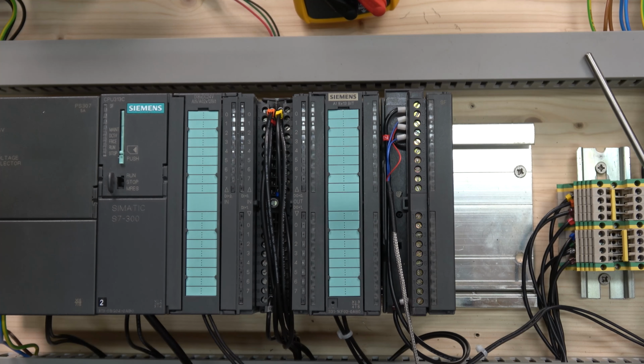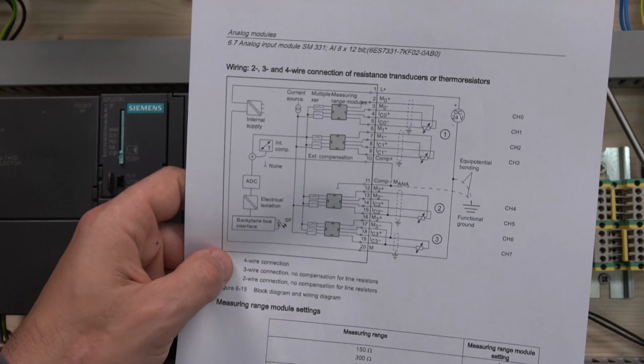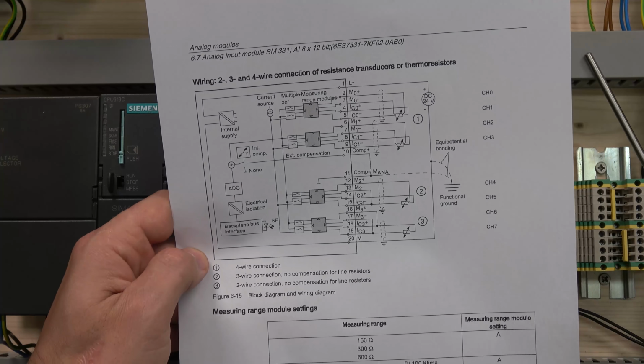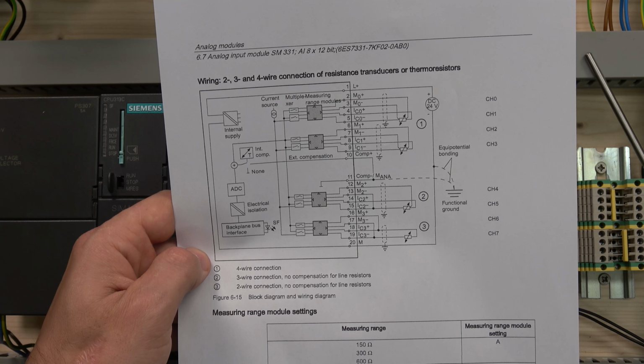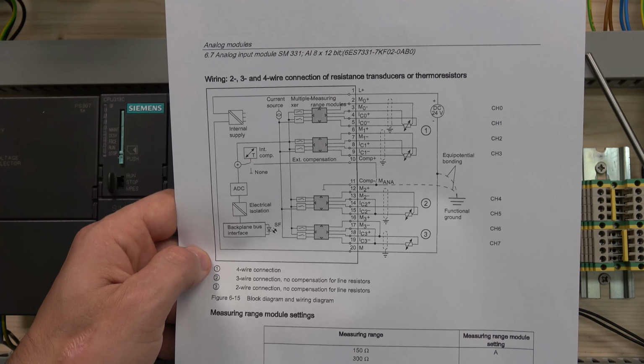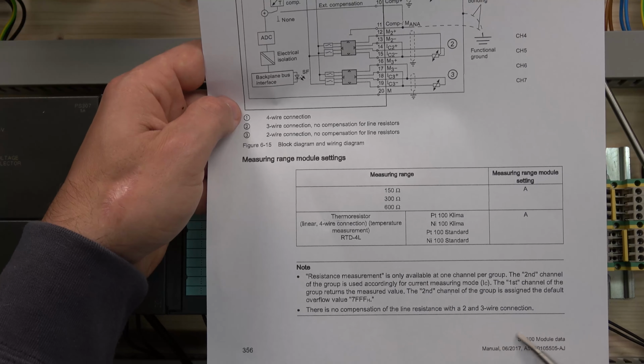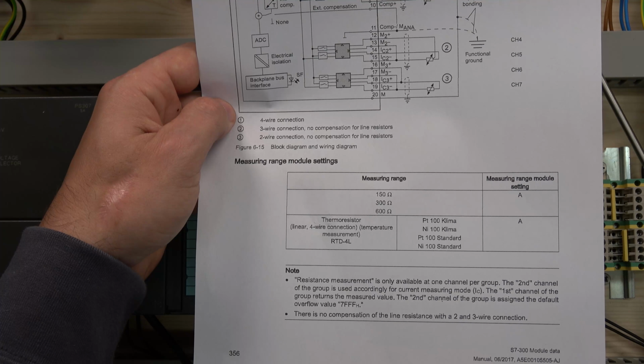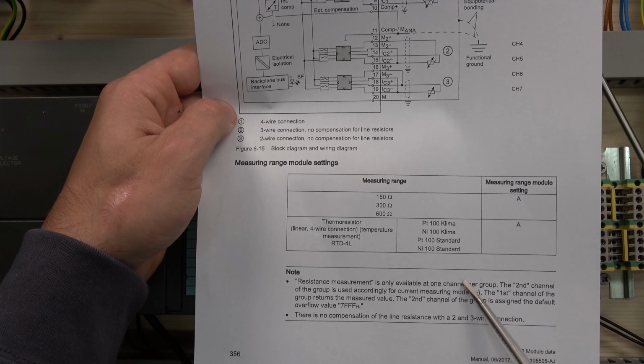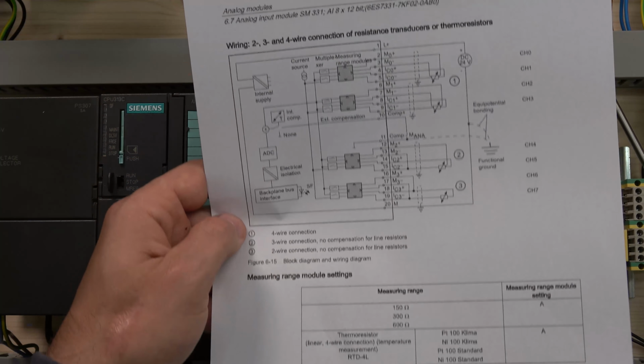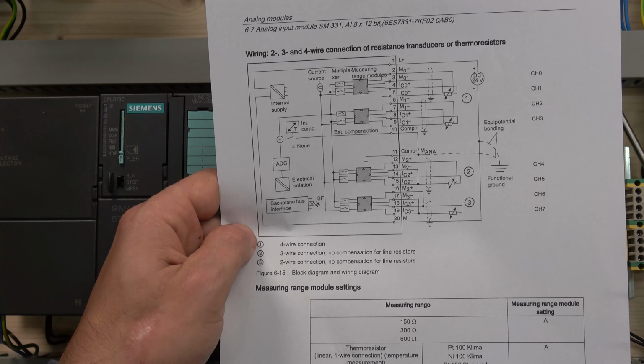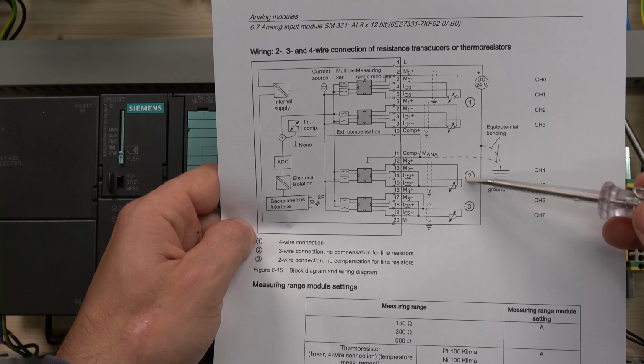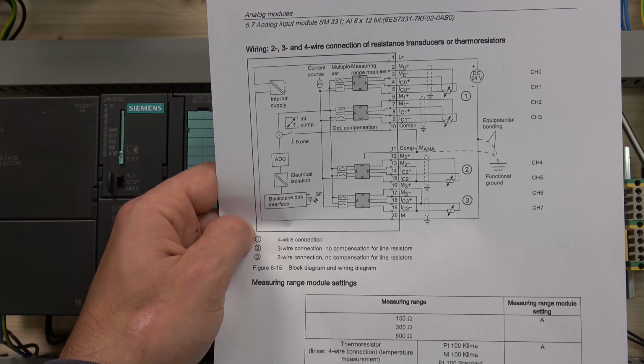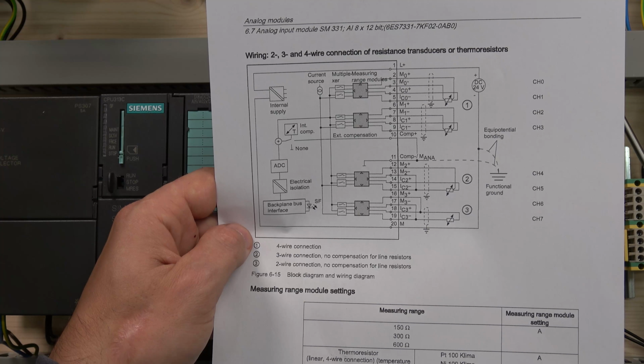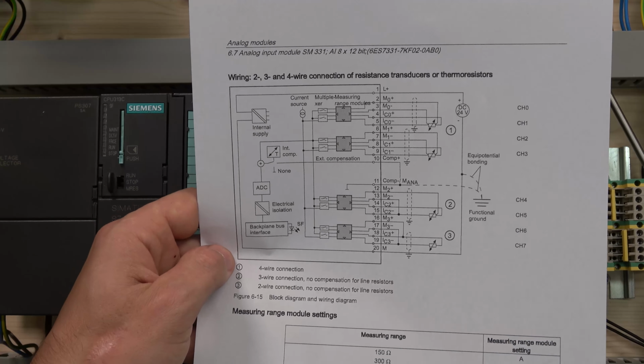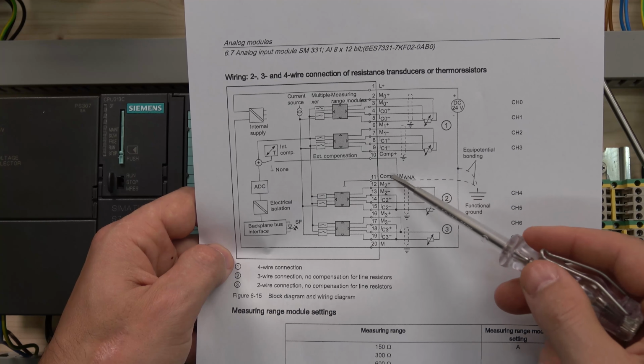So when it comes down to the wiring, this is the wiring diagram. If you want to have a look at this as well, we have a couple of options. We got a 4-wire, 3-wire, and 2-wire. All these probes can be used for the RTD family. It's already in here, it sort of explains to you how the display is going to look within your program, what the first channel does, what the second channel does, and so on. And it gives you the diagram as well. This one in here is for 4-wire, and this one in here is for 2 and 3-wire. The most common PT100 probes are 3-wire, at least the ones I have come across, it doesn't mean other ones don't exist. So we're going to be doing this wiring diagram.